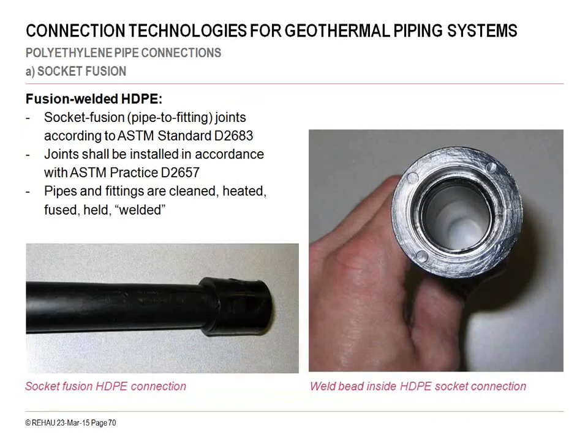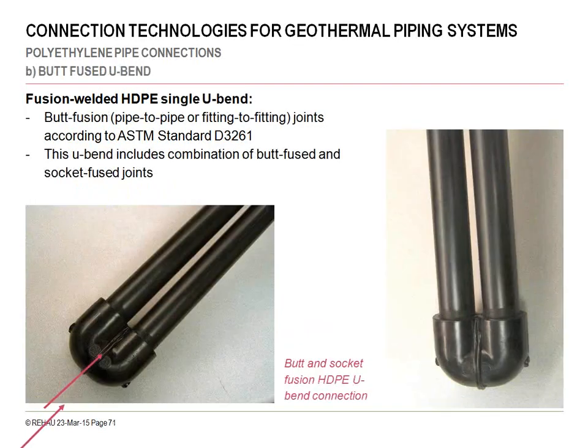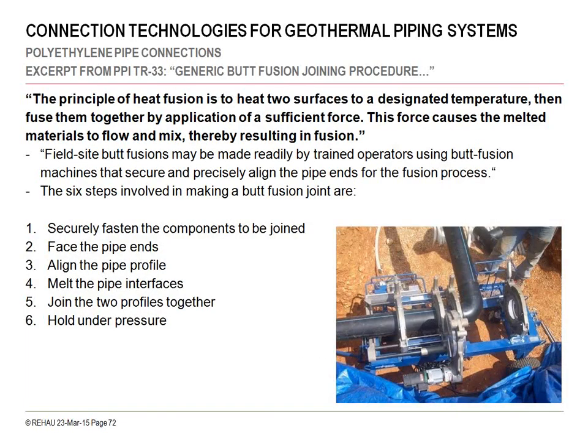And this is just some images here on socket fusion with Hdpe. It's really, as I said, melting and joining the two materials together. It's almost like welding, if you will. A fusion weld, fusion joint, and as mentioned, you would have joints at the bottom of the U-bend loops. Here's some butt fusion with Hdpe pipes, and you're joining these two under some pressure and holding the two pipe materials against each other after they've been welded.